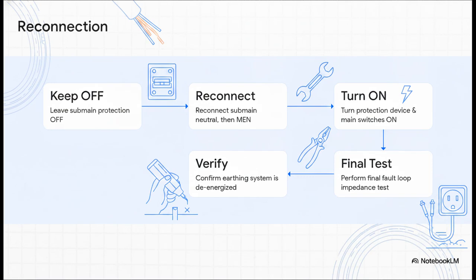After proving polarity with those exact same voltage checks we discussed earlier, we hit the reconnection phase, and you must maintain a fail-safe mindset here. Leave the upstream protection off. Then, reconnect the submain neutral first, followed by the MEN. Only after that do you restore power. To wrap it all up, perform a fault loop impedance test at a convenient socket outlet to verify that MEN integrity, and use a proximity tester to confirm that absolutely no part of the earthing system is energized.